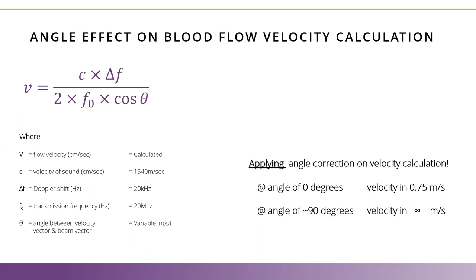To better illustrate this at different degrees, I'm showing you this graph, where you can clearly see that with an increasing angle, you will get a higher calculated flow velocity. But what does that mean in a practical setting? Because this is often the practical setting when you're doing a flow velocity measurement. Here you can see that ultrasound imaging probes are relatively large, and it is quite difficult to position the mouse and the probe in such a way that the angle is as small as possible, to decrease the angle effect in your measurement.